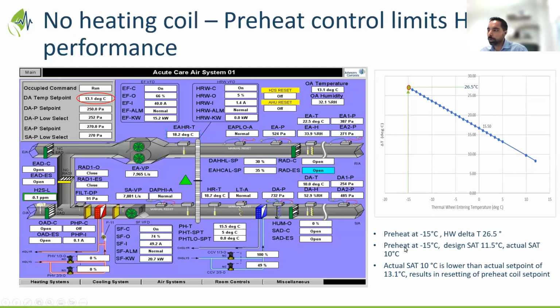This is one of the hospitals where they actually implemented the changes that were recommended. So they started with -10 as a preheat and -15. What was happening was, at -15, if you're entering air at -15, you would expect the delta T across the wheel to be 26.5, which at a design level would take you to around 11.5 degrees C. However, we're seeing around 10 degrees or around 8 degrees C on that system. So there is potentially a little bit of underperforming on the wheel side that could be improved if it's brought back to design.